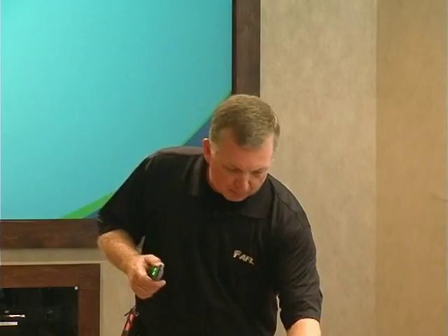And I watch it over days, taking a reading every 5 minutes for days and weeks and months. Then I know what it's supposed to look like at this point on that pole. All of a sudden something happens and it gets out of tolerance. Not an outage, but the waveform gets goofy. That's a technical term, goofy. Then that would set off a flag.